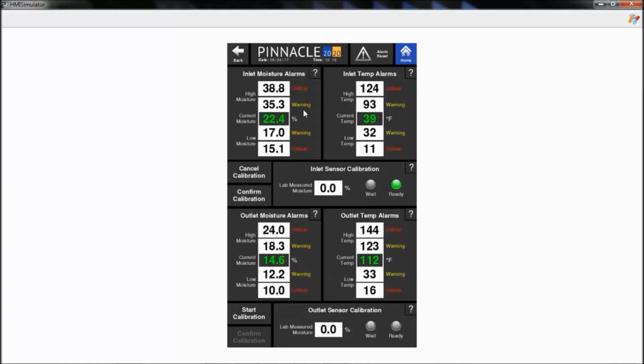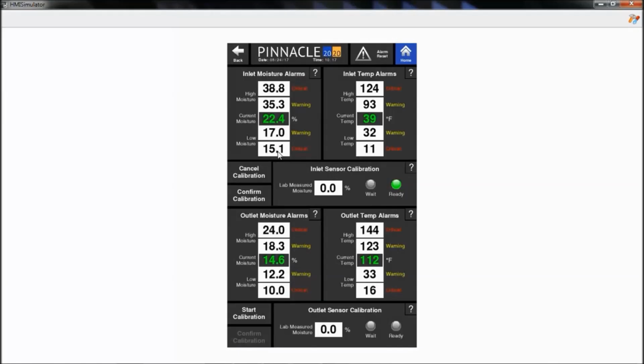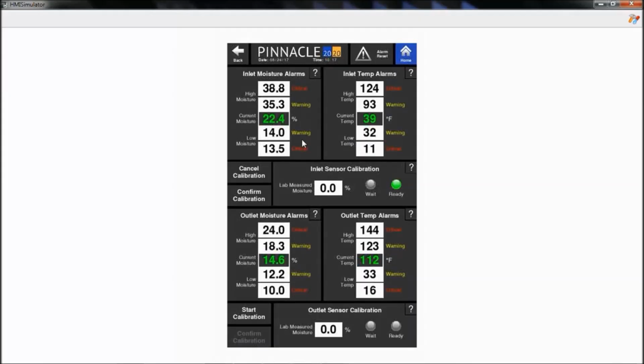A couple notes here. One is that all of these alarm settings are bound by one another. What I mean by that is that your low warning alarm cannot be lower than your low critical alarm, and it can't be higher than your high warning alarm. So right now my low critical alarm is 15.1. My high warning alarm is 35.3. If I were to change my low warning alarm, I'll see that my minimum is 15.1 and my maximum is 35.3. So if I want to change this value to something lower, let's say 14%, I'll first need to change my critical to something below 14% so that I can now go into my warning alarm and change it down to the 14 that I desired.